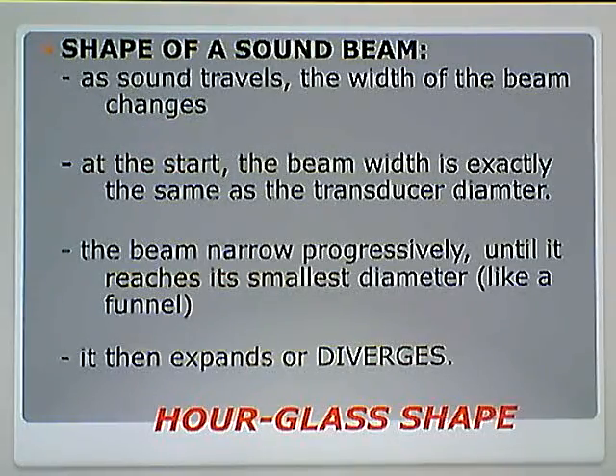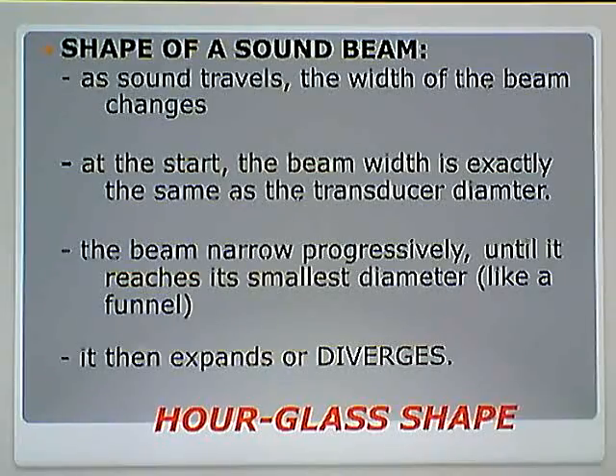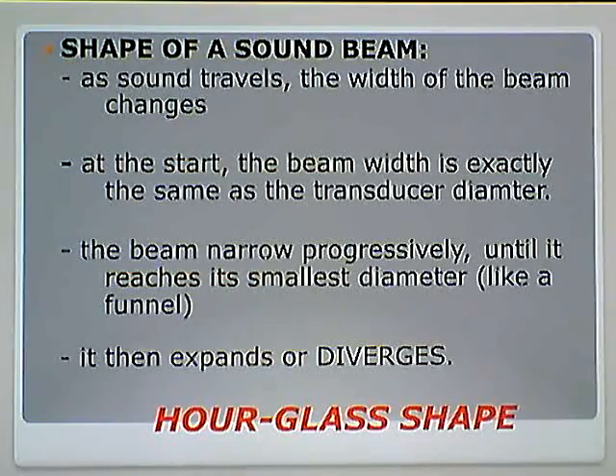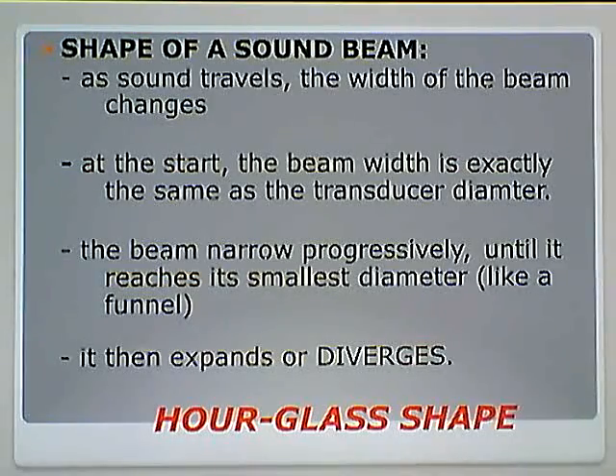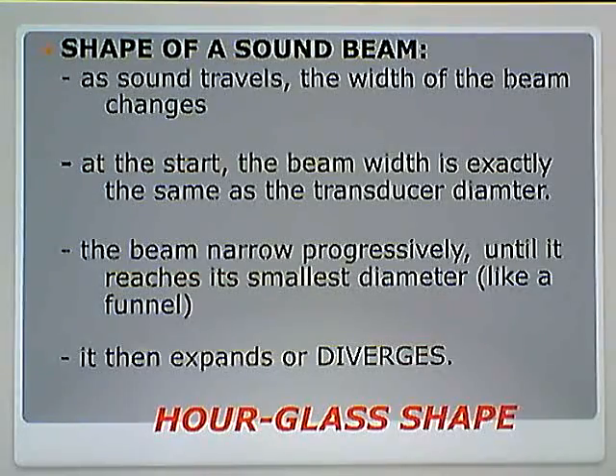The shape of a sound beam — this was all very easy. We understand that it is an hourglass shape. When it starts, it's the width of the transducer. It narrows until it gets to the smallest diameter, and then immediately begins to diverge — the hourglass shape.